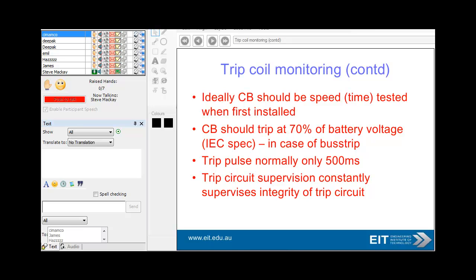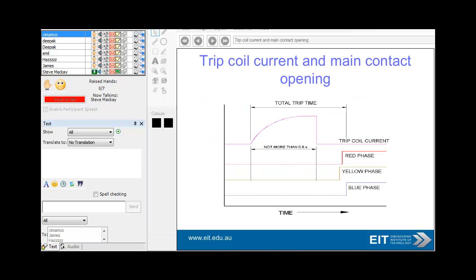For trip coil monitoring: high-duty circuit breakers should be speed-tested when first installed. Circuit breakers should trip at 70% of battery voltage in case of a bus trip. The trip pulse is normally only about 500 milliseconds. The trip circuit is usually constantly checked to verify the integrity of the trip circuit and ensure it is operating correctly.